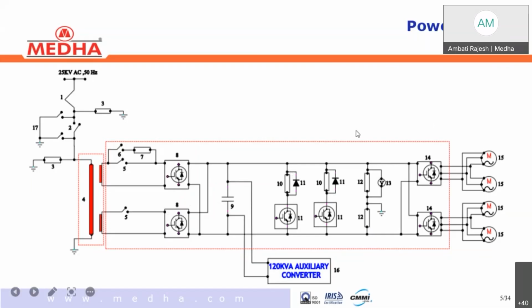Initially, for the first time, the system energizes this precharging contactor, so that through the precharging circuit it starts converting this single phase AC into DC. Whenever it reaches 90% of the required voltage, the system energizes the main contactor, so that these 2 contacts get closed and both line converters start working. The function of this IGBT based line converter is to convert single phase AC into constant DC with unity power factor at the input side. It rectifies and maintains a constant 1800 volts DC with unity power factor at the input side. That is the function of these two line converters.